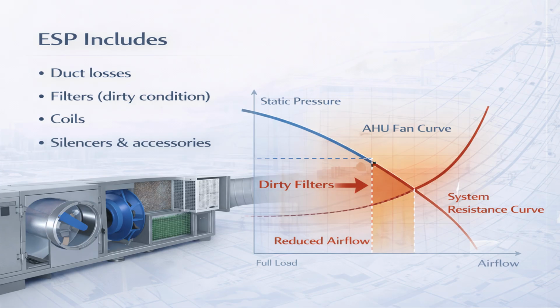Fan static pressure is one of the most commonly underestimated parameters during HVAC unit selection. In many cases, units are selected using a nominal or typical static pressure value, assuming ideal duct routing, short runs, and clean components. But real systems are never ideal. In practice, fan static pressure must overcome the combined resistance of the ductwork, the cooling or heating coils, filters, especially as they load with dust over time, as well as the sound attenuators, dampers, VAV boxes, and other terminal devices. Each of these elements adds pressure loss to the system.